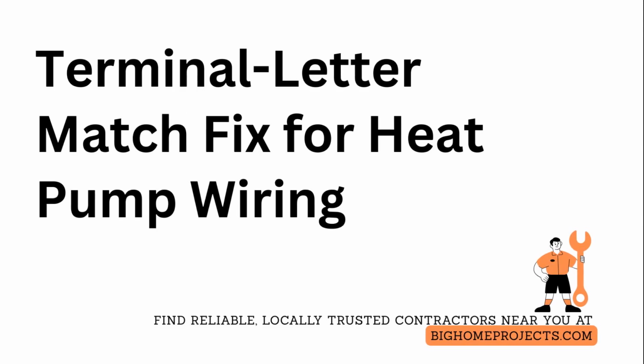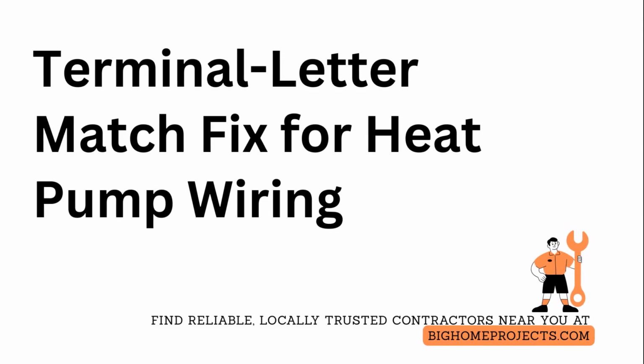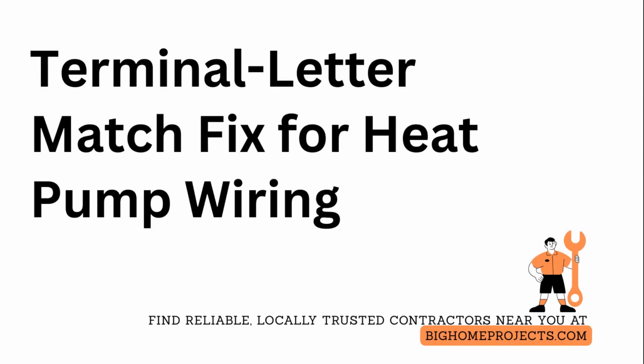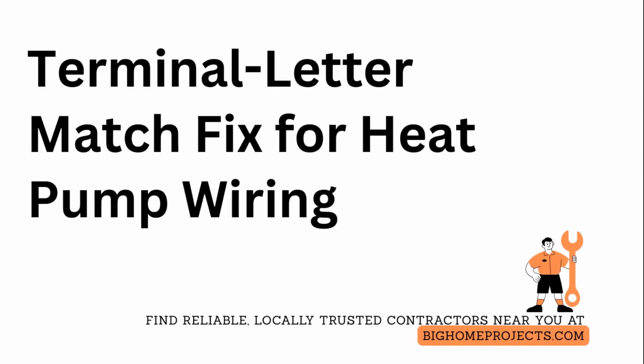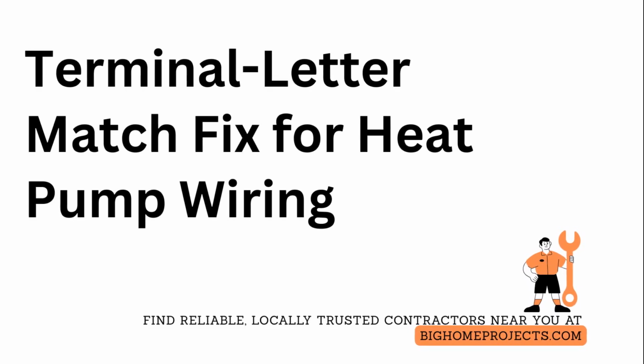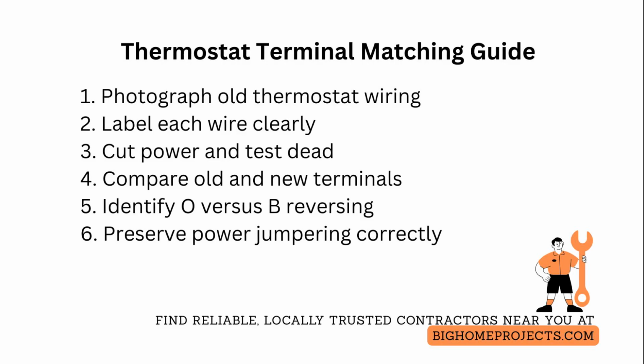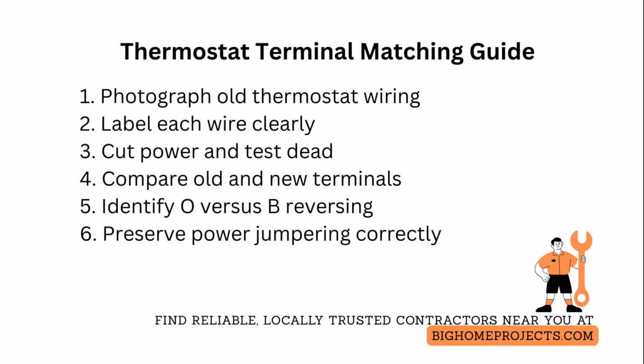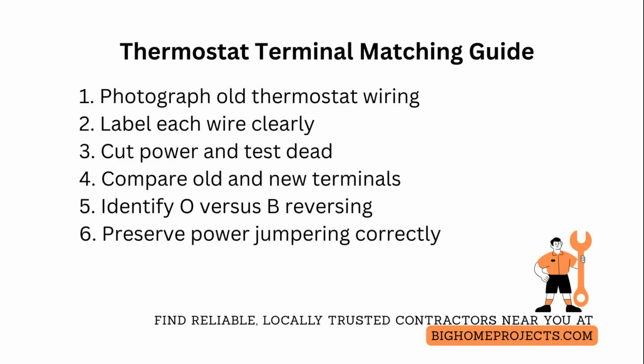Upgrade your thermostat without frying your HVAC. Always verify that each thermostat terminal letter matches the control board terminals before connecting wires. When replacing a thermostat, treat the wiring like a map. Take a clear photo of the old stat with the cover open, then label each wire with masking tape and a pen to preserve terminal letter identity.